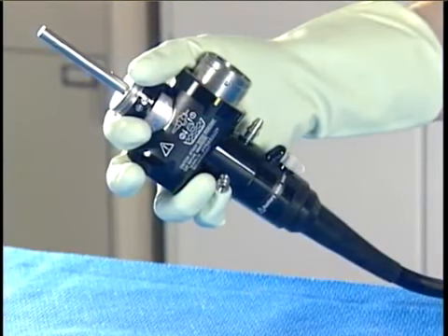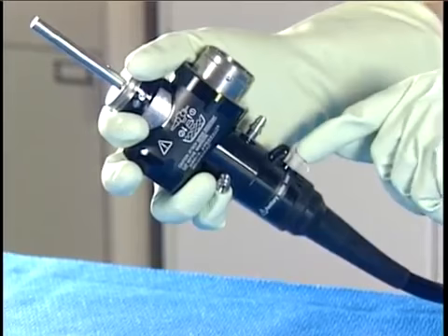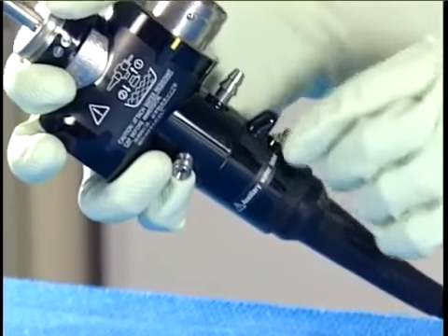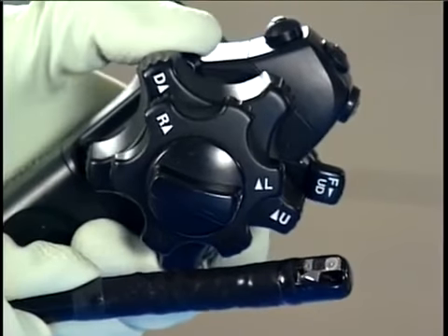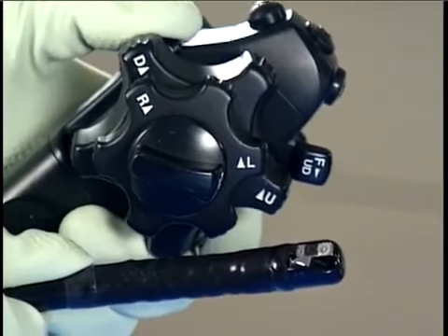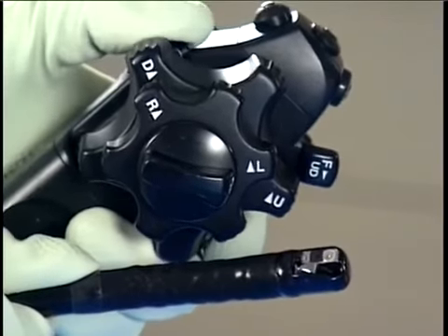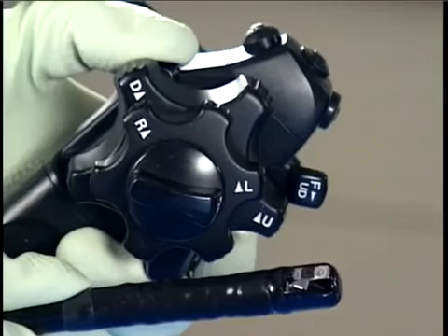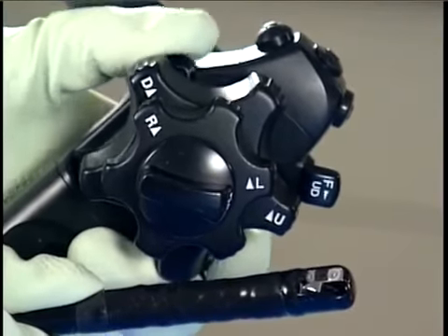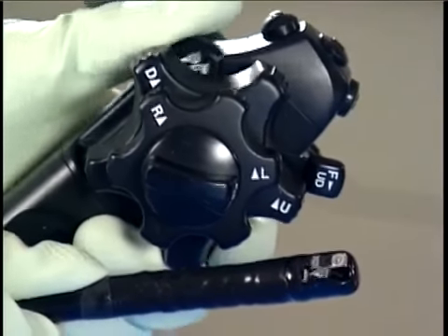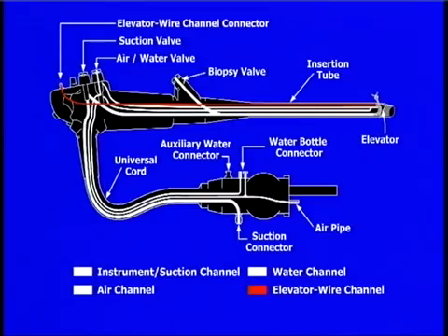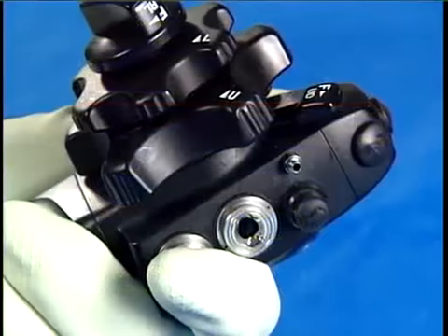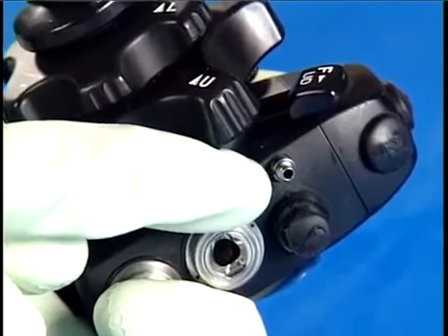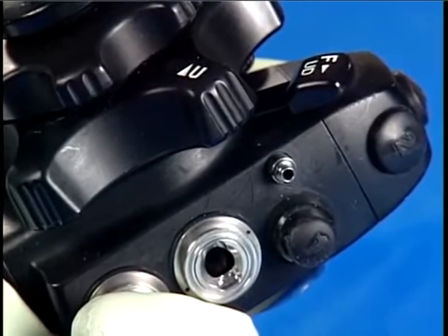If your endoscope has this special auxiliary water channel, you will find a connector for this channel on the light guide connector of the endoscope. ERCP endoscopes or duodenoscopes also contain a special channel. All duodenoscopes have a distal movable part called an elevator that is used to manipulate accessories which have been passed through the biopsy channel. The wire that controls movement of this elevator runs in a channel called the elevator wire channel. You will find a connector to access this channel on the control section of every duodenoscope.